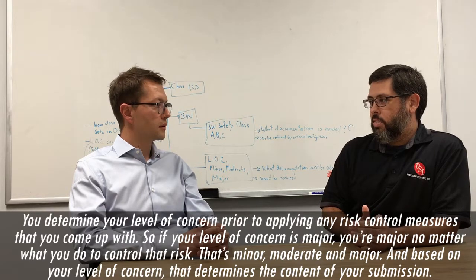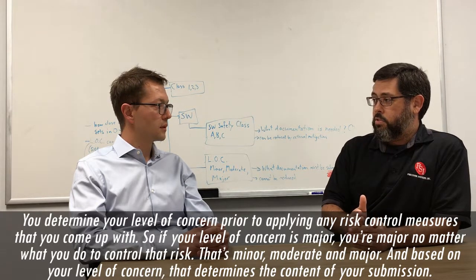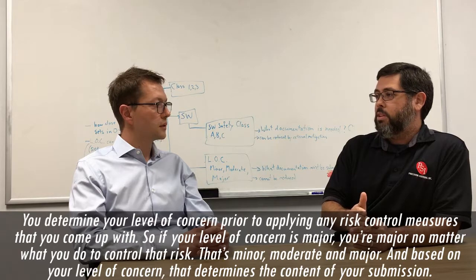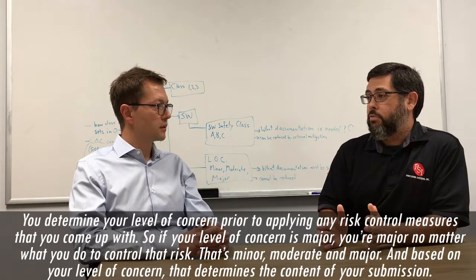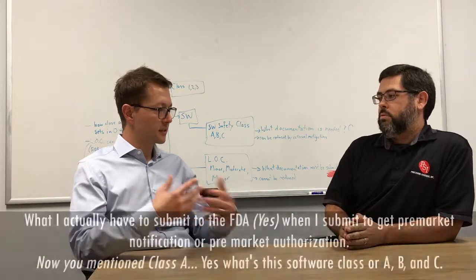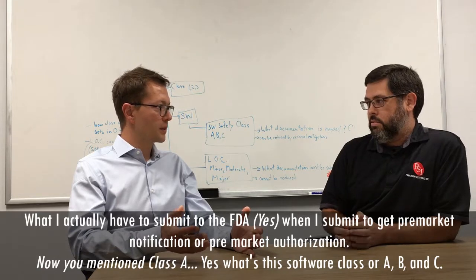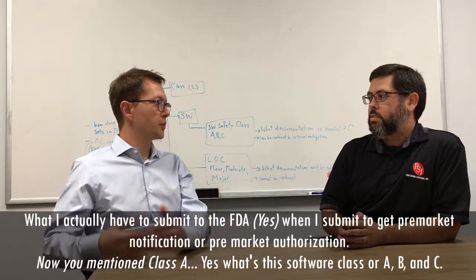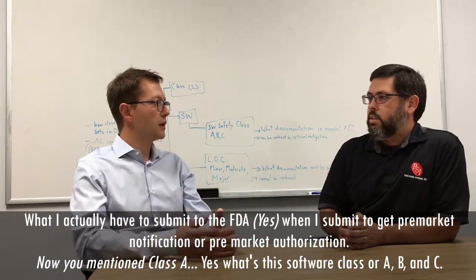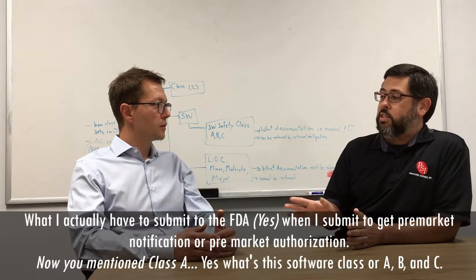And based on your level of concern, that determines the content of your submission. What I actually have to submit to the FDA when I submit to either get pre-market notification or pre-market authorization. Correct. Okay. Now, you mentioned Class A, B, and C.